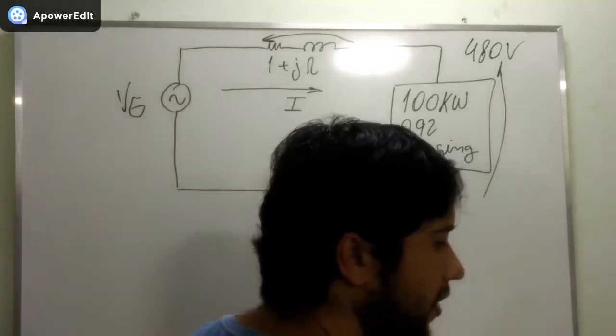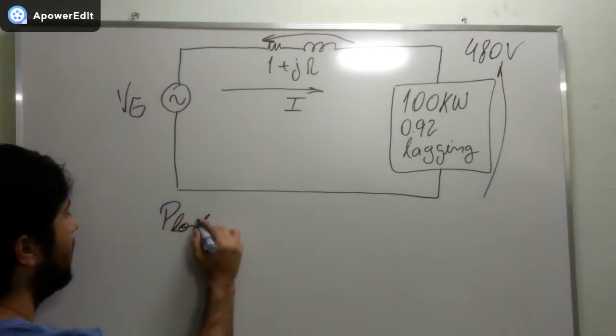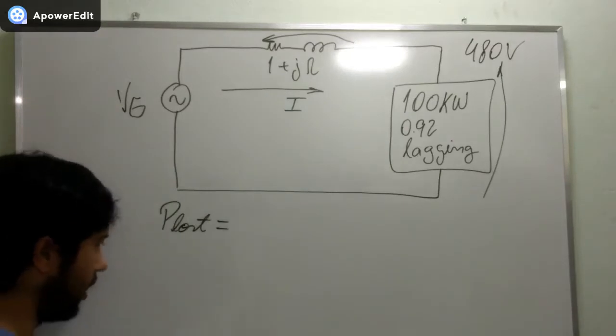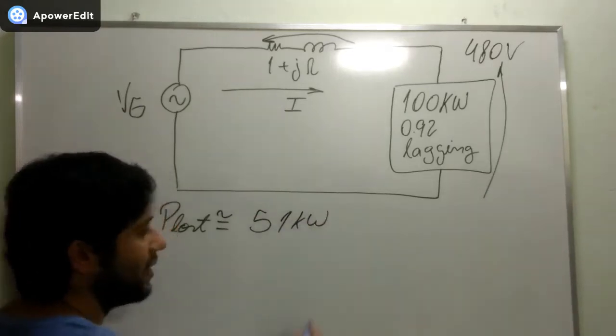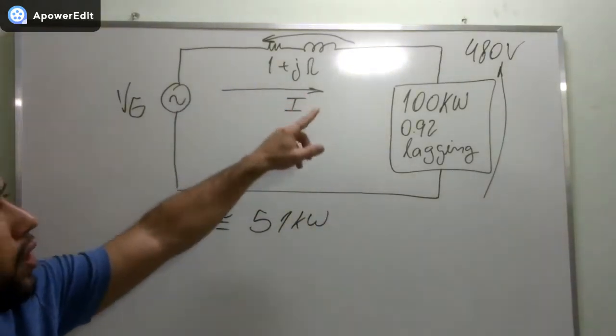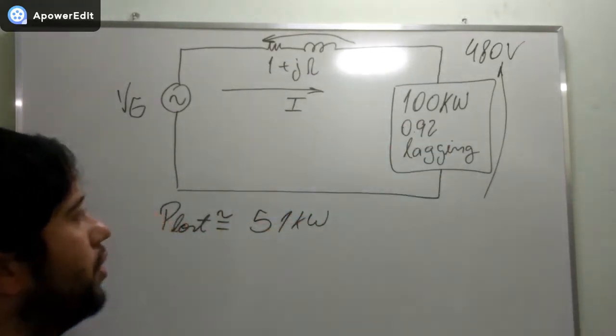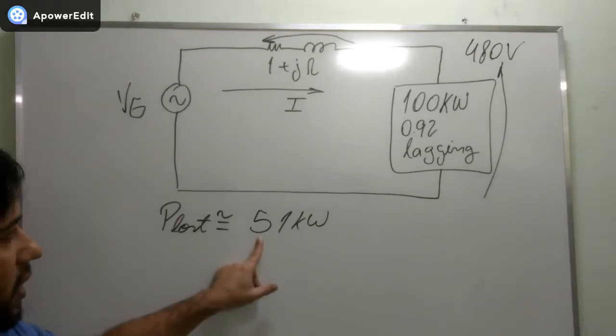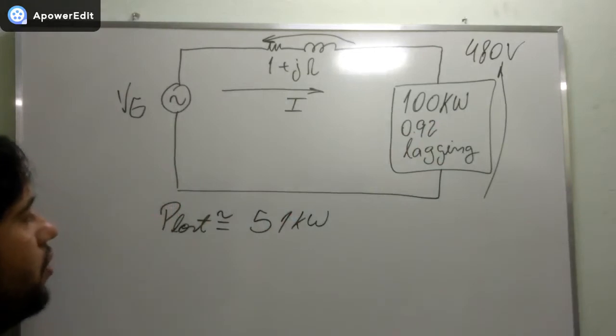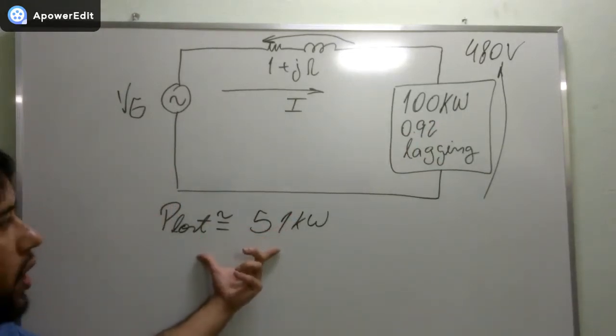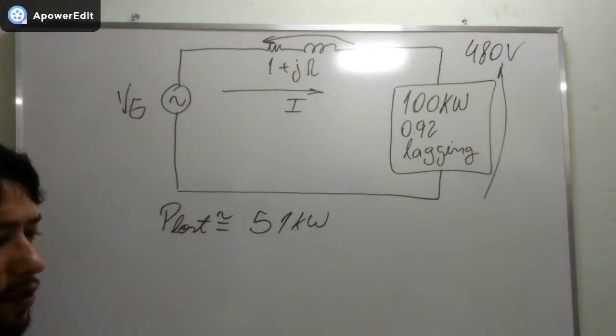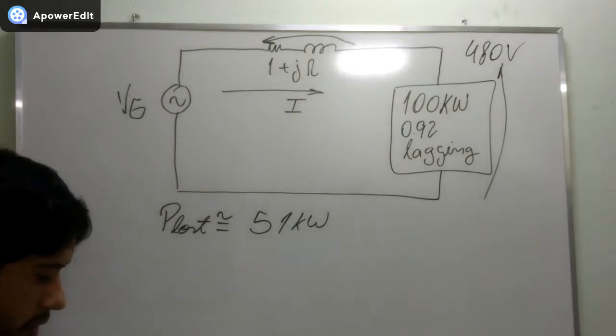The power lost in transmission with this configuration — without transformers — is approximately 51 kilowatts. That is roughly half the load power, meaning we are losing a huge amount of power in the transmission line that could be used to supply other loads. Save this value; we are going to use it for comparison.